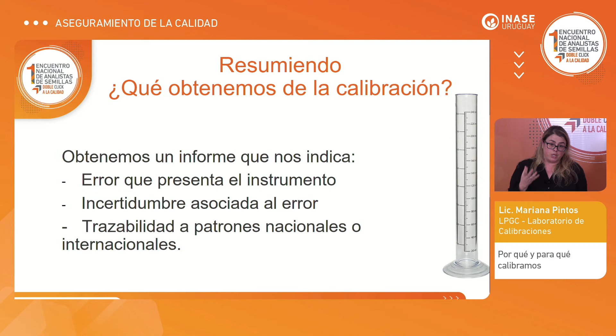So as a summary, what do we get from calibration? What is important? We get a report that is telling us about the error of the instrument we are using. So it tells us how we are measuring, and an uncertainty associated to the error. So it will tell us what's the margin where our value can fall, and traceability to national and international standards. So when I ask for a calibration, the lab is issuing a certificate, and it says it was calibrated with this scale and this certificate. How can I know about traceability, if there is a metrological traceability?